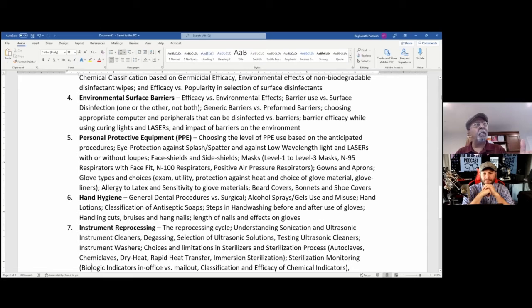Even for the instrument washers, they've taken care of most of it. At least in the US, I have not seen corroded hinges. The only time I see corroded hinges is when the sterilization or the drying cycle is not effective, or there's cheap humidity, or cheap Chinese instruments. Because the stainless steel we use here in the Americas has fixed carbon, whereas with the cheaper, softer stainless steels that you can get overseas, it's not, and you'll still get some rust and pitting on those.